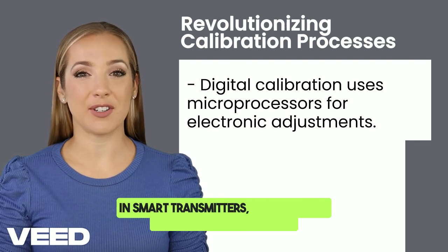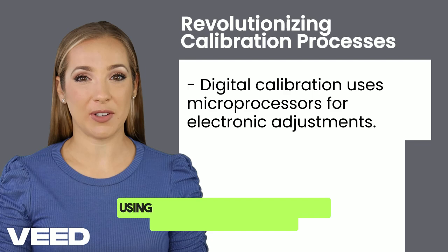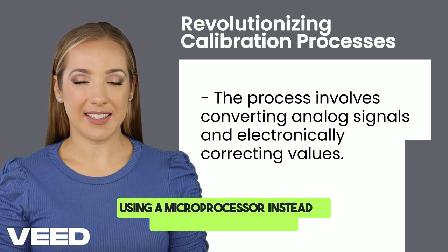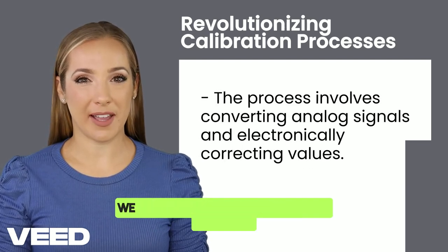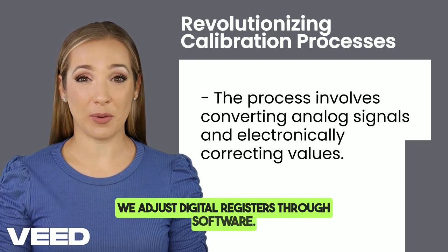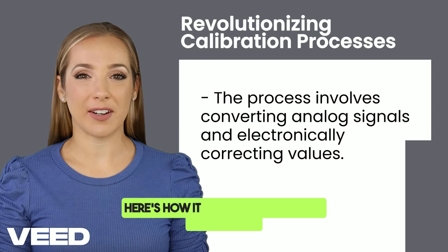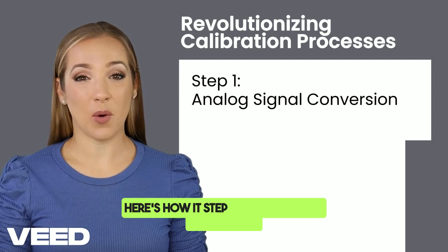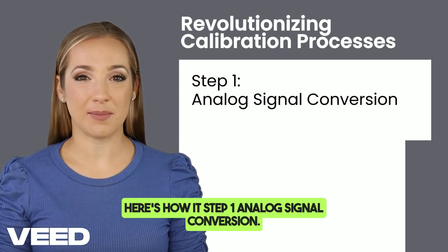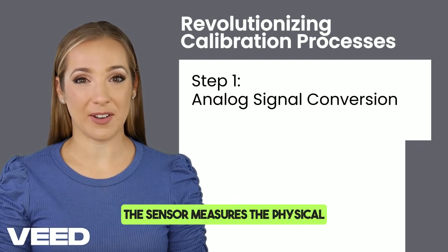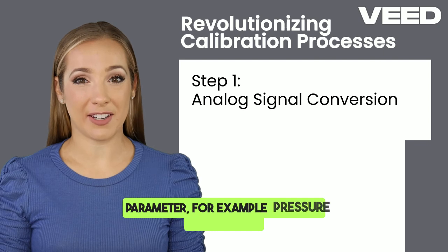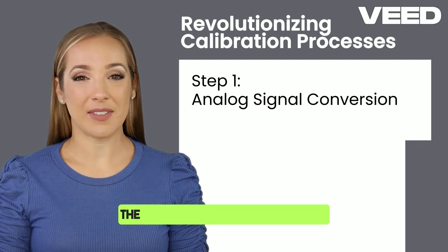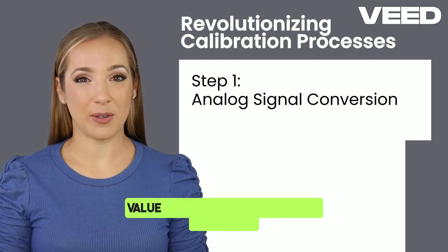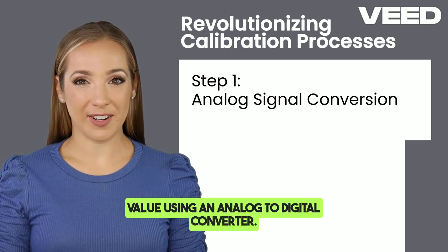In smart transmitters, everything is handled electronically using a microprocessor. Instead of manual potentiometers, we adjust digital registers through software. Here's how it works. Step 1. Analog signal conversion. The sensor measures the physical parameter, e.g., pressure, temperature. The signal is converted to a digital value using an analog to digital converter.